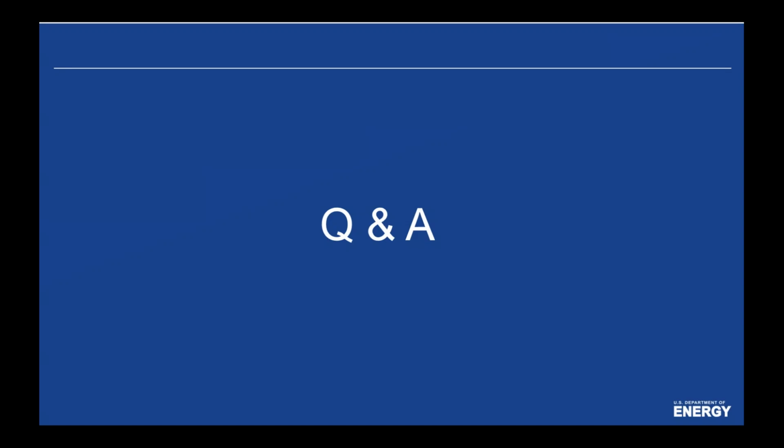Yeah, thanks. So on the first question, yeah, we do quantify carbon reductions from different technologies deployed on site. In the results panel, we give some information about the source of emissions, so if it's coming from grid electricity versus fuel that you've consumed on site. And because DER-CAM gives you the option to optimize for CO2 reductions, you can actually use that to drive the design outcome. Given that we use CHP, there are instances where that can reduce your CO2 emissions due to increased efficiency of serving thermal loads. But versus an all PV battery solution, it might not be as strong a CO2 reduction. So it really depends on how you construct your model, but we do give you information for that.